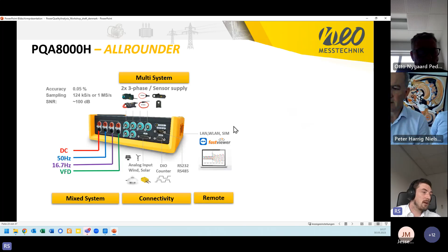So regarding the instrument, we have multiple inputs. So we see here from the voltage side, a channel to channel and channel to ground isolation. So we are also possible to measure DC and AC or mixed signals actually, or common mode signals, because we have a quite high signal to noise ratio. Then for the current inputs, we have these multiple inputs, where we have the possibility to have the integrator inside. So if you think about the Rogowski coil measurements, this gives us a huge advantage, because we can measure with the same coil actually 1 amp or 30,000 amp. So this is possible in the same way here.